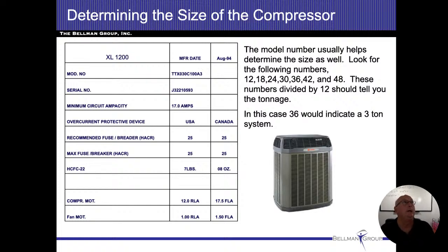All right. The next thing I want you to look for is the maximum breaker. Sometimes that's listed as maximum fuse that's on there. Now, in our company, we always take a photo of the data plate. All right. This is a big deal to us. We take a photo of the data plate, and when we go inside the electrical panel, now we have a reference that we can go back to.